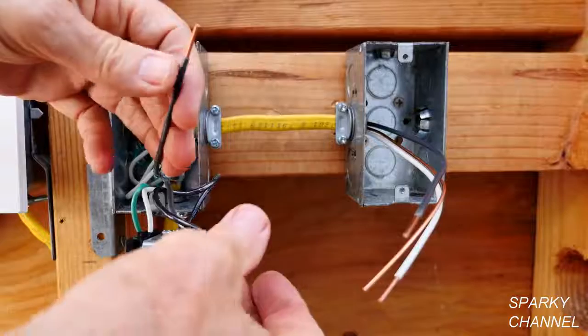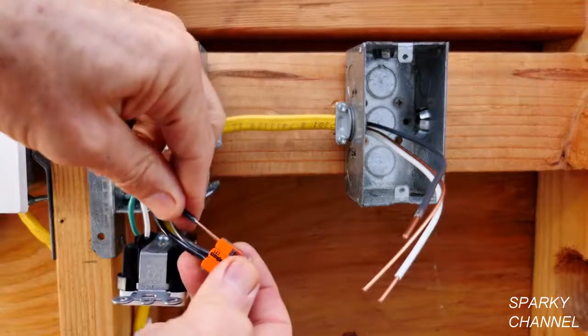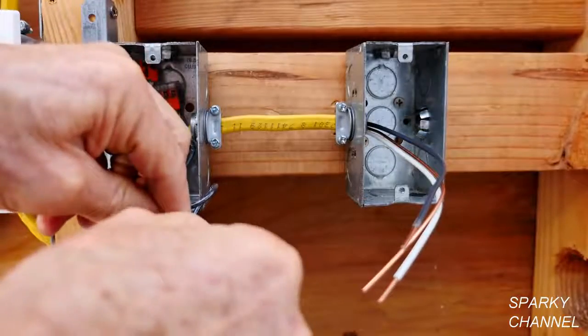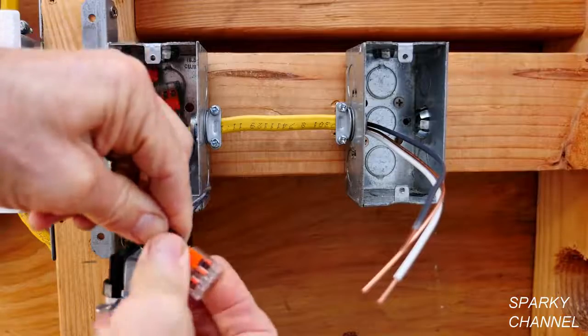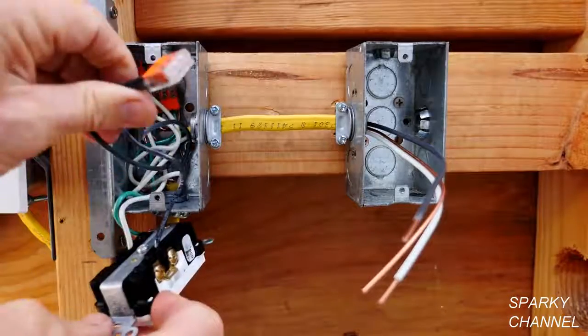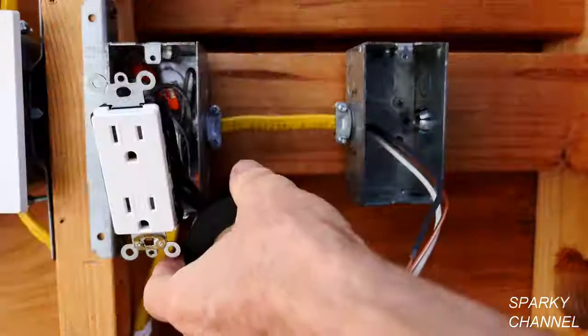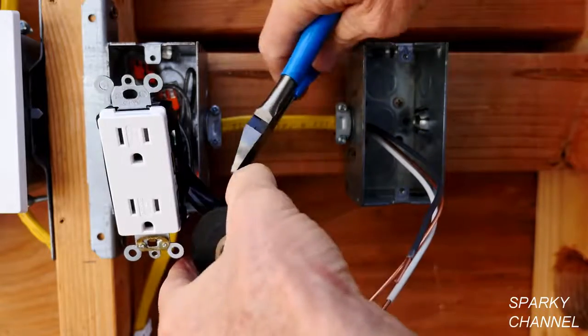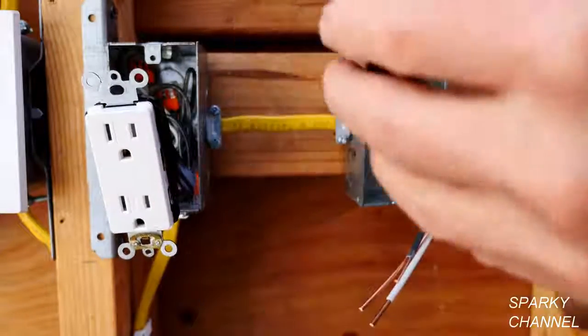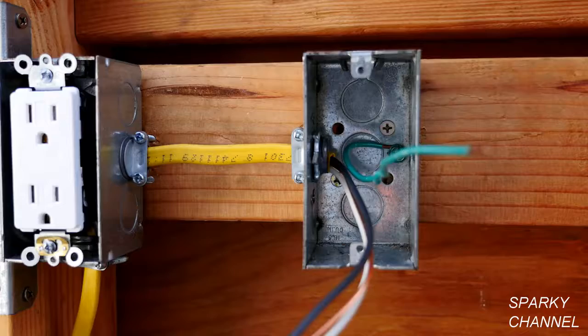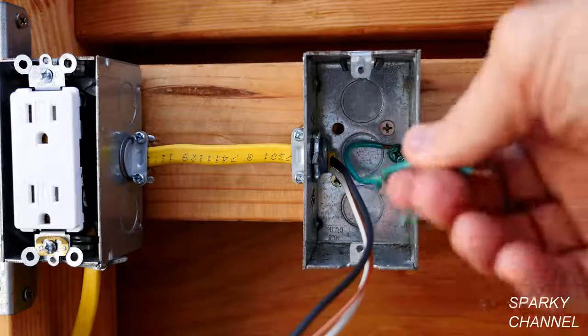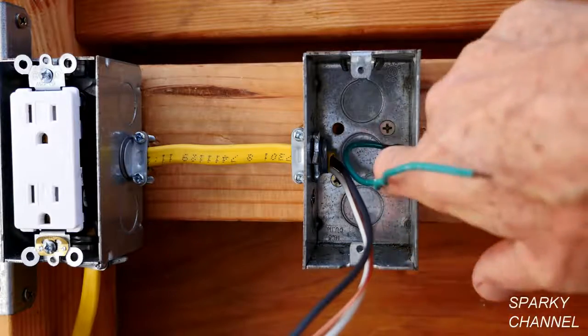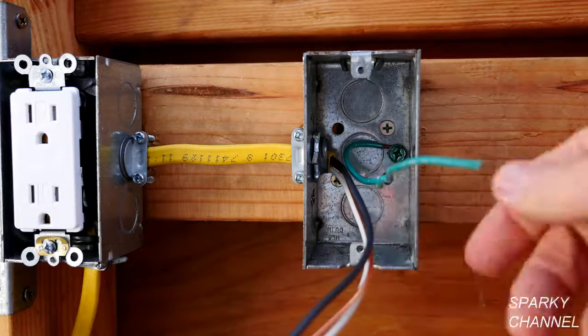Now we'll hook up the hot. Open up the Wago lever nut, put it in, click it down, and we'll push this into the back of the box. Now I'll put a couple wraps of black electrician's tape around the receptacle for safety. I have now added a grounding pigtail to the box. I have firmly connected it with the screw right here.